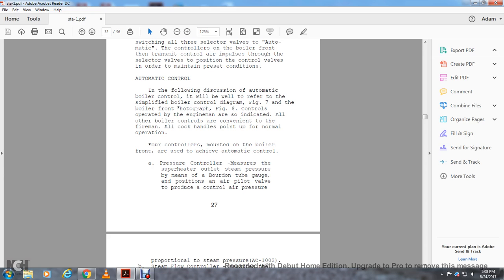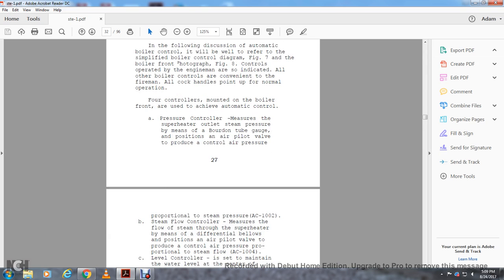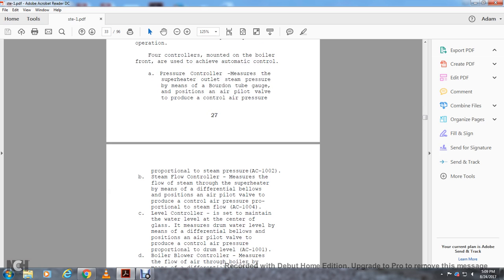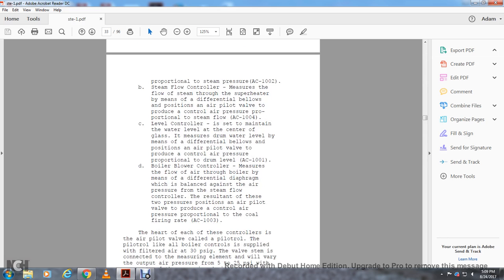Pressure controller measures the superheater outlet steam pressure main with the Bourdon tube gauge. It positions the air pilot valve to produce the control air pressure proportional to the steam pressure, AC 1002. Steam flow control measures the flow of the steam through the superheater by the differential bellows, and positions the air pilot valve to produce the control air pressure proportional to steam flow, AC 1004. Level control is to maintain the water level at the center of the glass. It measures the drum water level with the differential bellows and positions the air pilot valve to produce the control air pressure proportional to drum level, AC 1001.